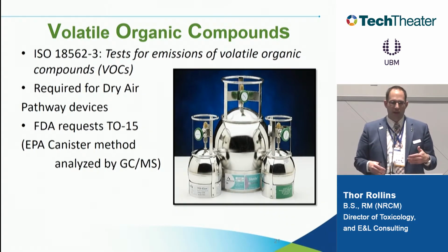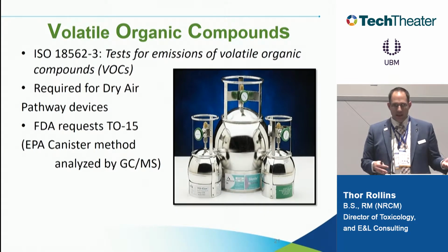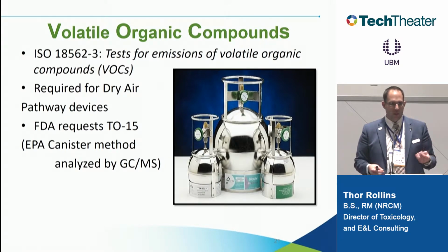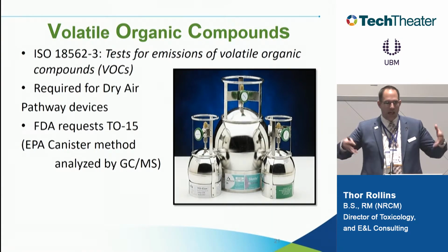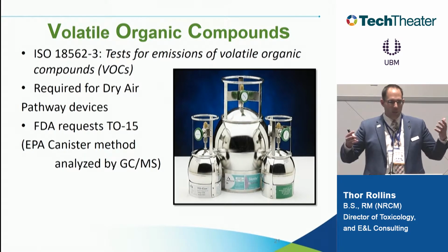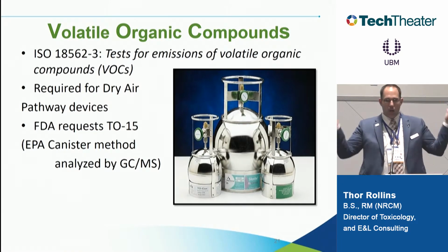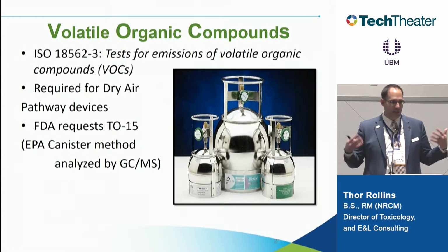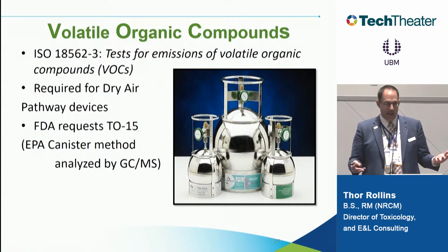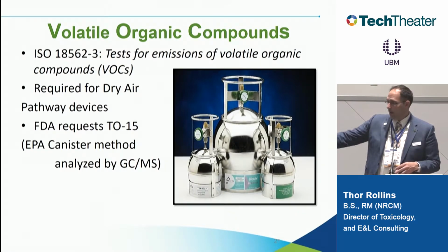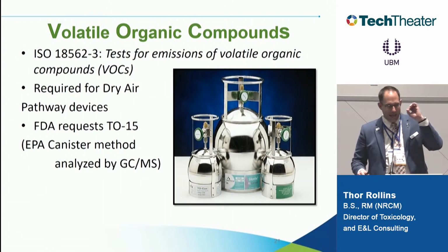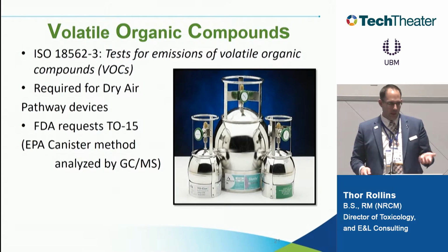This is much better than running fluid through it to catch the fluid to look at what volatiles, or heating up the whole device, right? If we put that whole device under a glass case and heat it up, well, that's not clinically relevant because now all those chemicals from all that material are leaching into that test. And if you pass, that's great, but if you fail, what does that mean, right? This way, we're able to get just the gas path tested under clinical conditions.